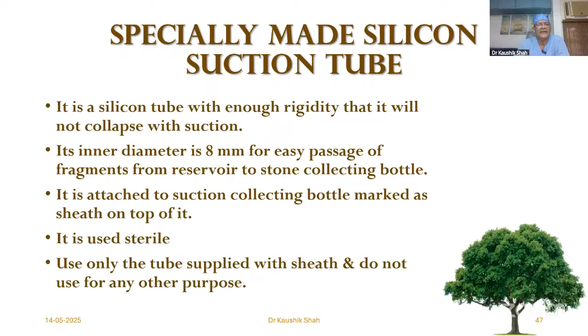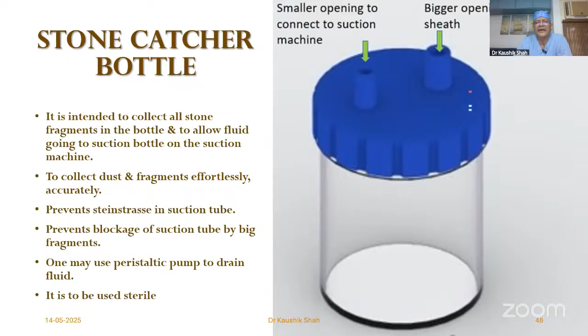Now the suction stone catcher bottle, the fragments which come get collected into the bottle, and only the fluid goes to the suction machine. So it is very easy to collect all the stone plus the stone fragments, which may have to travel a long distance to reach the suction bottle. So there will not be any steinstrasse or blockage in the suction tube, and also it is used sterile and it can be autoclaved.